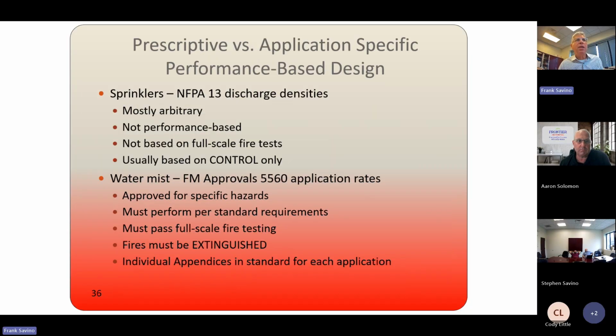Okay, moving on. So again, we have application specific versus prescriptive. Sprinklers, in NFPA 13, the discharge densities are pretty much arbitrary. They go all the way back to pipe schedule days, and they really haven't changed much. They're not performance-based. They're not based on full-scale fire testing, and they're usually intended for control only.